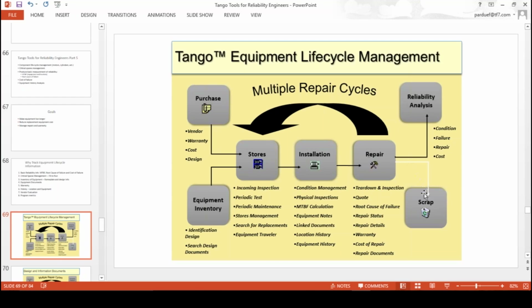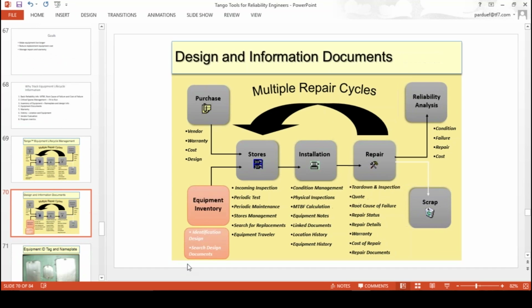At our previous discussion, we talked about the repair tracker. We talked about scrapping a piece of equipment and doing an autopsy. But even if you are scrapping a piece of equipment, it's important to know why it failed, so that information can go back into the metrics you're producing for that type of equipment. So then you get a lot of reliability analysis that comes from aggregating all this information over a large population of motors or breakers. Let's look at the area of equipment inventory to begin with.